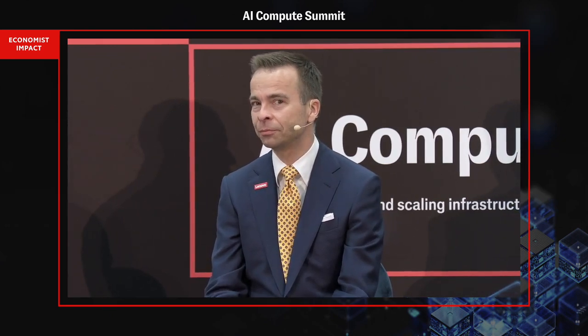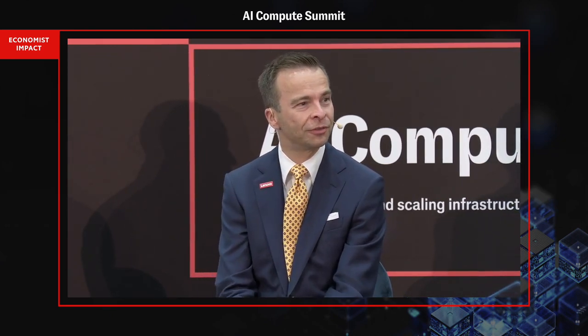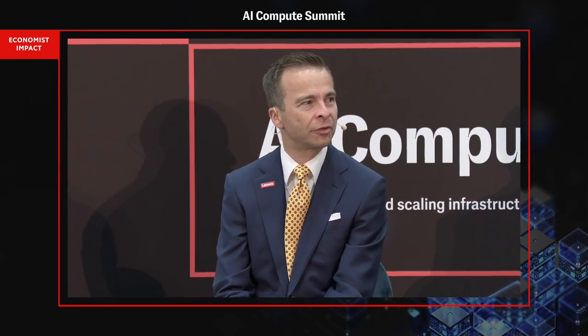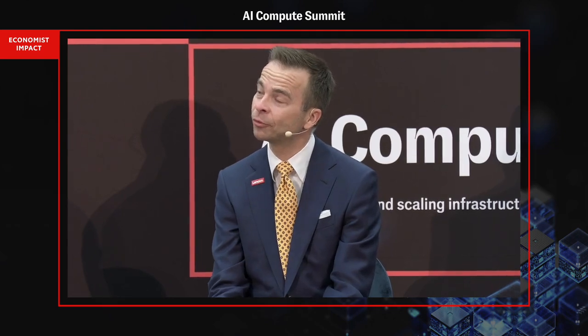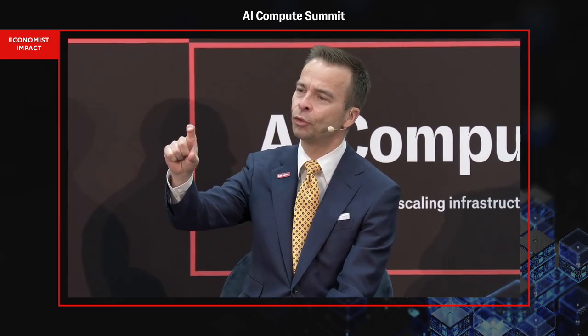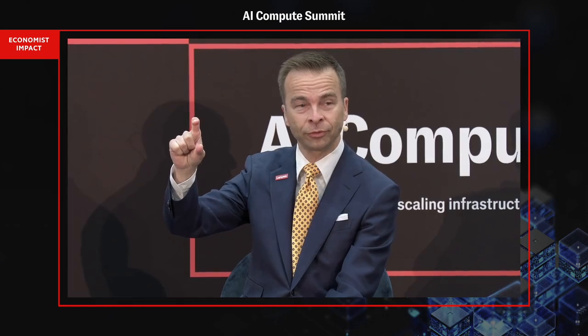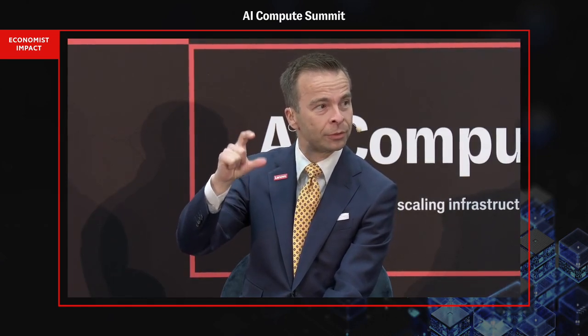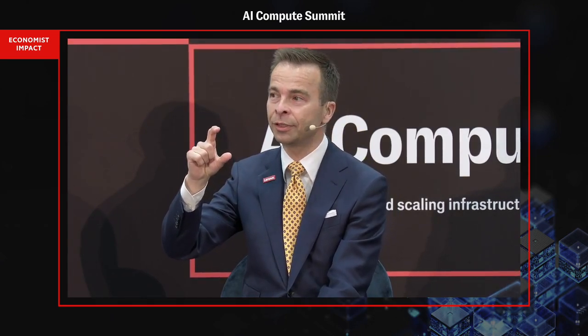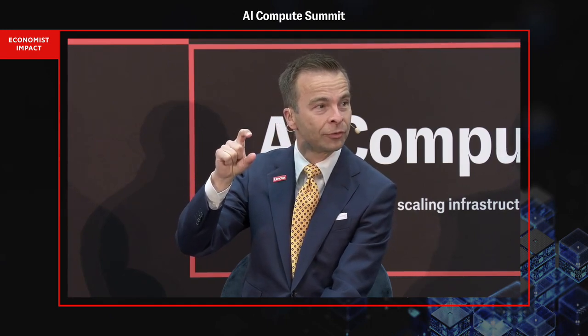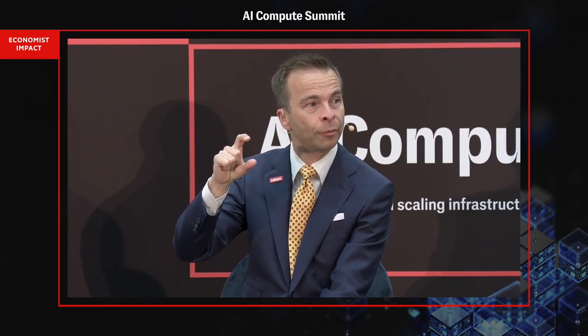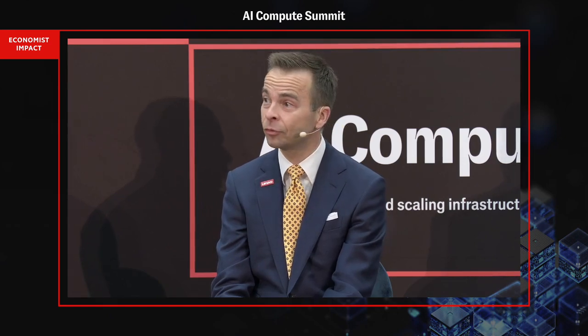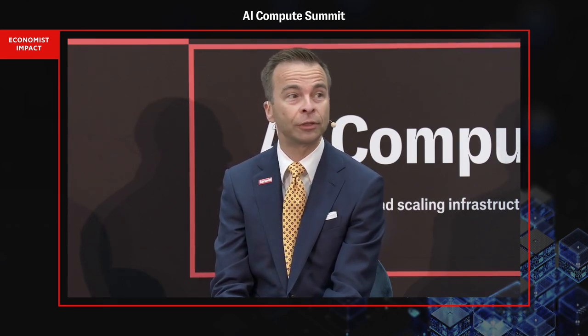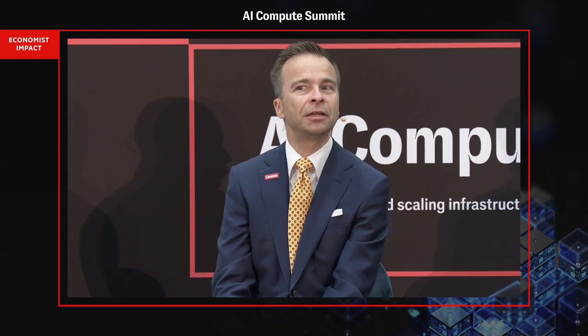If I asked you to guess how much power fans take in servers these days, most of you would probably say a single-digit percentage. You're very wrong, I'm afraid. If you look at even a single-CPU server, not even a GPU server, well loaded like in an HPC environment, you'd easily see 20% plus, going up to 30% of total server power going to fans. So you're wasting 20 to 30% of the energy, the operating cost, on moving hot air. I don't think anyone's paying you for that, but you are.